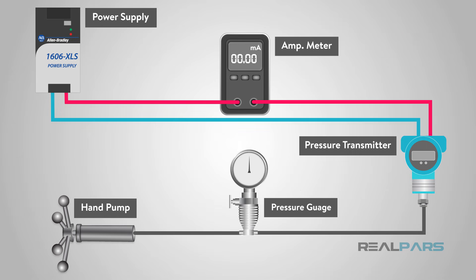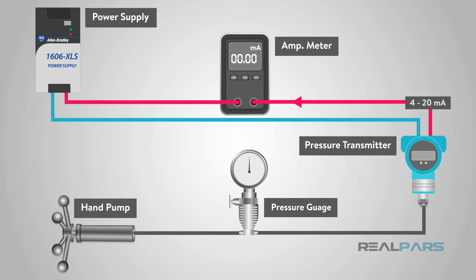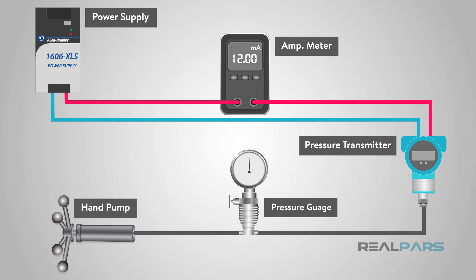To calibrate, we need a very accurate process simulator — in this case, a pressure supply connected to the process side of the transmitter. A current meter is attached to the output to measure the transmitter's 4 to 20 milliamps output. Ideally, a National Institute of Standards and Technology calibrated simulator and current meter are used. In practice, we can use very accurate process meters and pressure input modules.